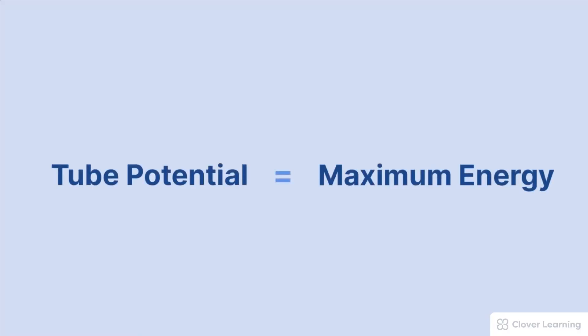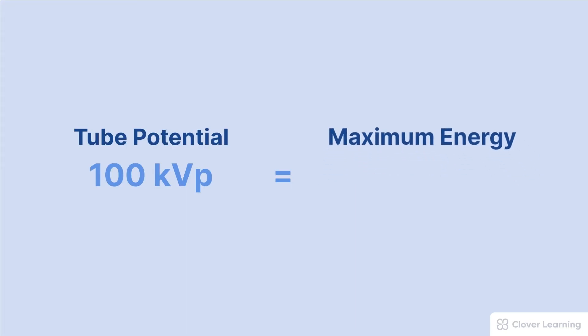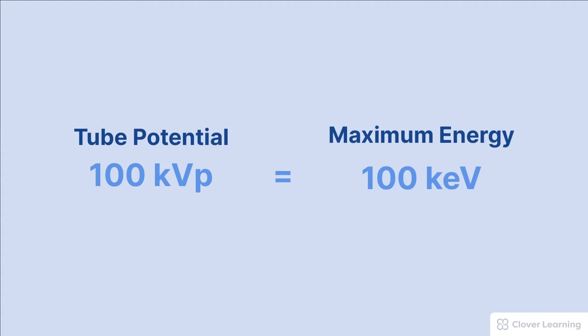The mathematical relationship between KVP and the x-ray beam energy is actually very simple. The KVP is mathematically equal to the maximum beam energy. So in this example, if the KVP is set to 100, the maximum energy photons in the beam are going to be 100 KEV. Not all photons in the beam will have 100 KEV, but some will. KEV is an acronym that stands for kilo electron volts, and that's just the unit of measure for quantifying the energy of x-ray photons.